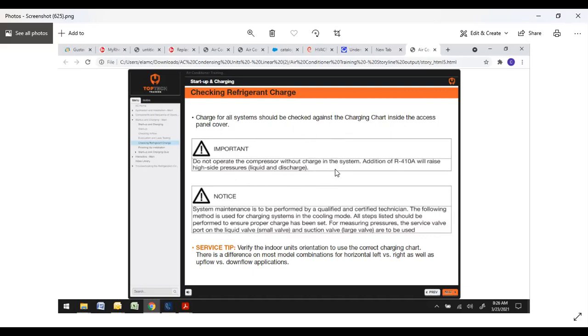Important, do not operate compressor without charging the system. Addition of R410A will raise high side pressure. Notice, system maintenance is to be performed by a qualified and certified technician. The following method is used for charging in cooling mode. So if you have an air conditioning, it's specifically going to give you cooling mode charging. If you have a heat pump, it'll give you options for both cooling and heating.